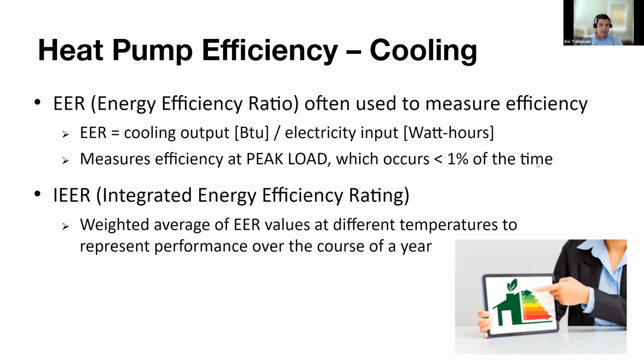So as Alex mentioned, VRF systems are really good at part load, and that's where the IEER comes in. That's the integrated energy efficiency rating. This is a weighted average of EER values at different temperatures to represent performance over the course of a year. So this looks at your EER at 25%, 50%, 75%, and 100% of your cooling load, and then weights that to give a better representation of what is actually happening with your system during the cooling operation seasons.